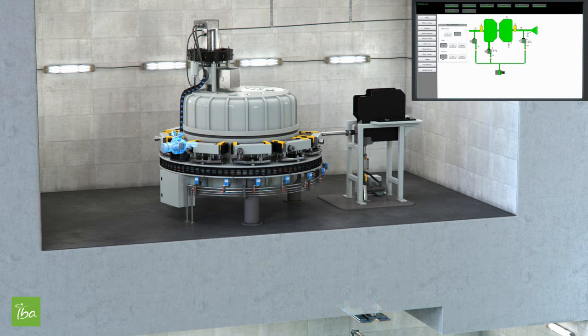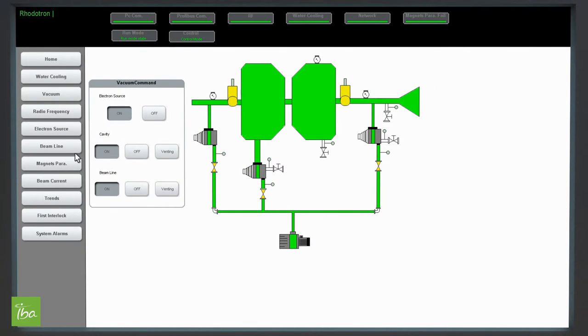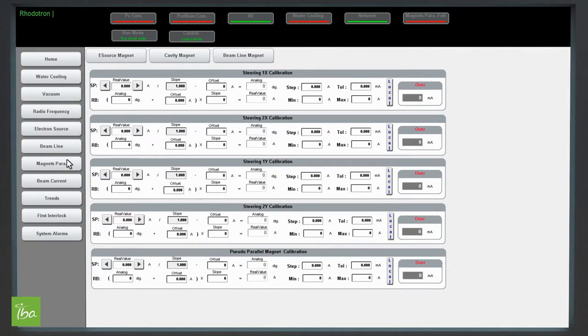The same is done with the electron gun. This will remove the molecules of air that could generate collisions on the electron path. Now turn on the nine magnets around the machine. The purpose of these magnets is to bend the electron beam and recirculate it inside the machine.